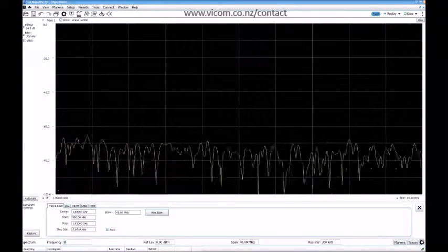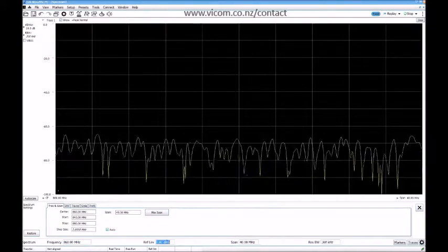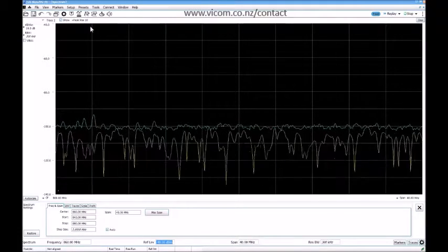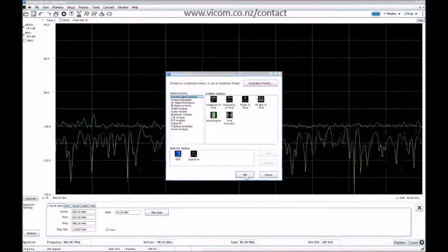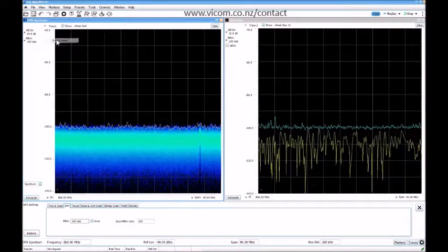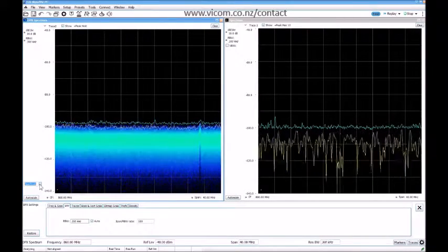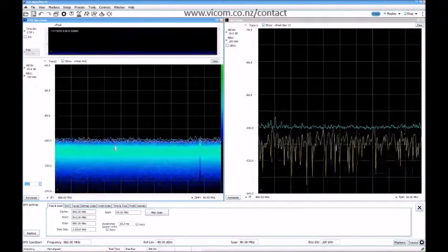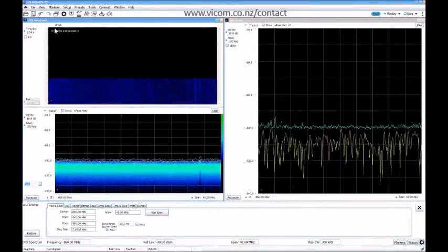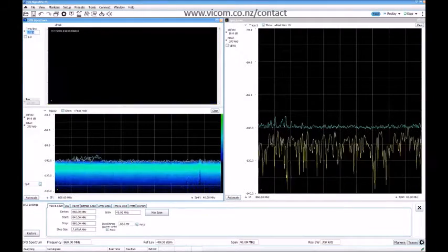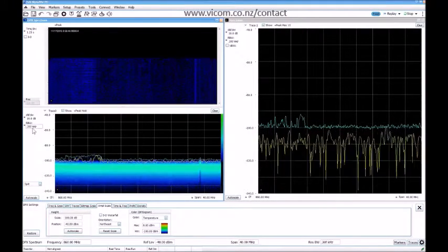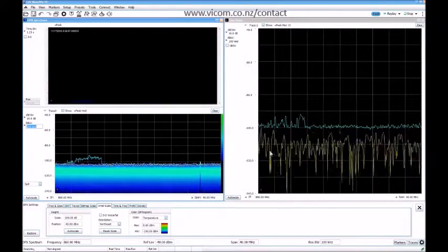So instead here we put 860 megahertz. We set the ref level down a little bit, more than 40. We enable trace 2 with max hold. I go in here, I press the DPX. I go for the DPX, I enable trace 2, so max hold. I go to a split. Like this, and I'm going to tweak this a little bit. Probably a little bit faster, it's okay. And then we have the amplitude scale. And we're going to reduce the bandwidth a little bit to 100.